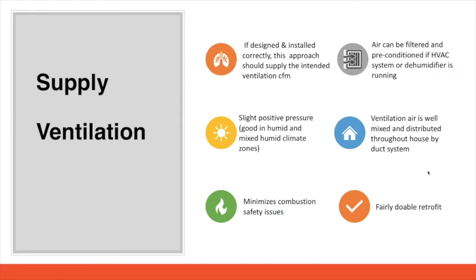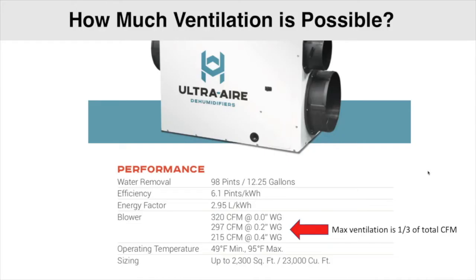And obviously, if the HVAC system's running at that time, we can get some precondition. We're going to mix that air really well before it's distributed throughout the house, and that is fairly doable in a retrofit situation. So how much ventilation is possible? We get this question a lot on how to figure out what size dehumidifier you might need for a house and how much ventilation you can get. And the max ventilation that you can get from one of our dehumidifiers is 1/3 of the total CFM.